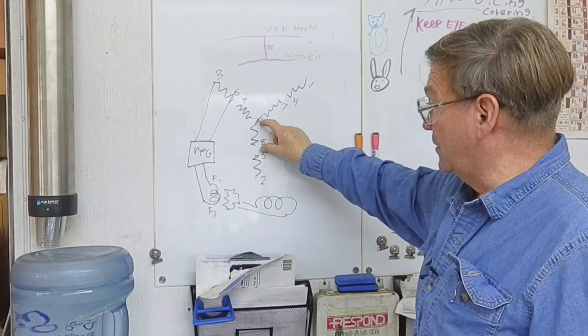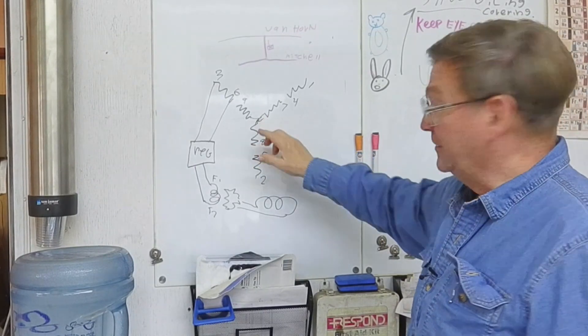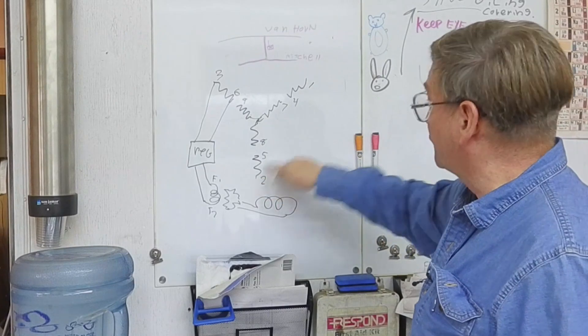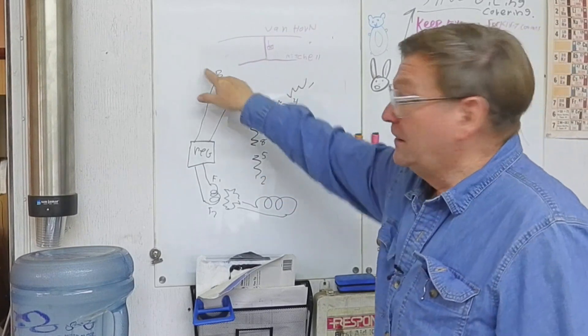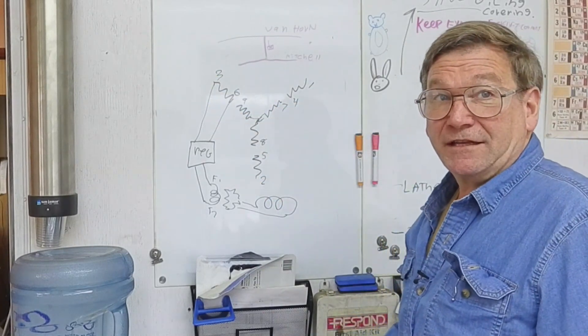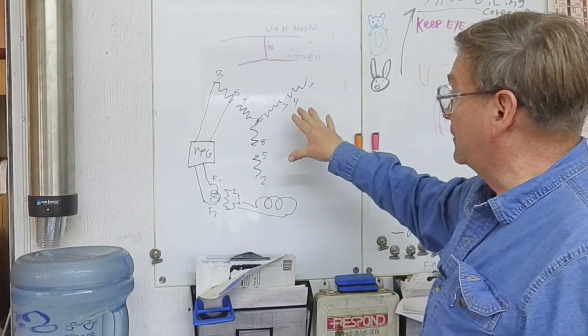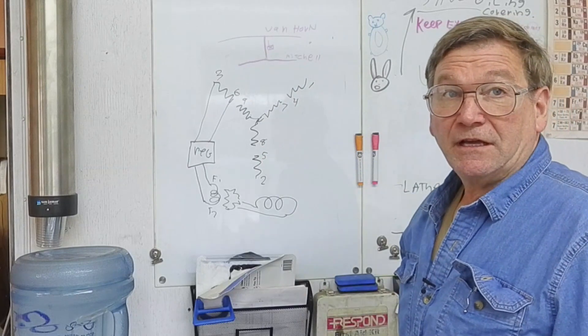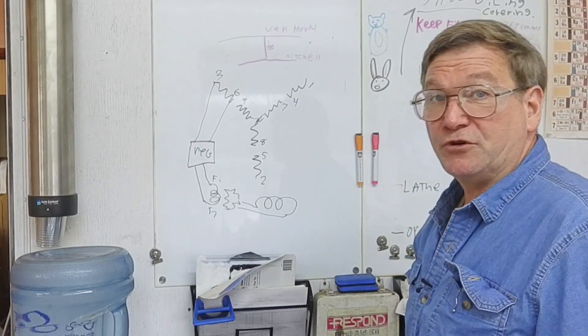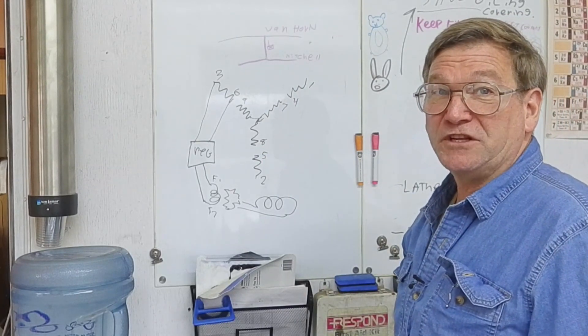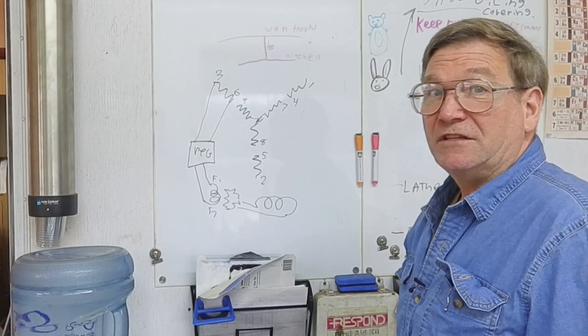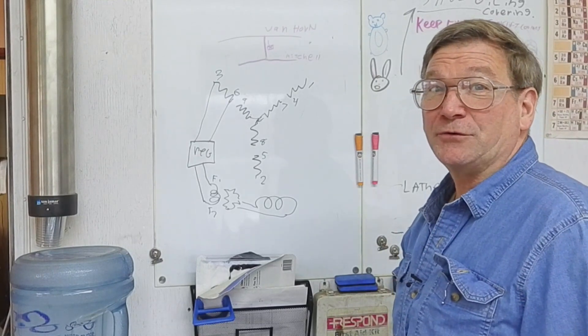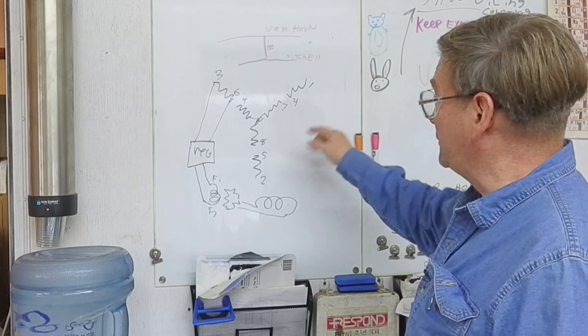Each of these coils are 120. Because of the angle is why you get 480 between here. That also depends on what your regulator is set to. But the big thing I wanted to draw out is the numbering system. While you'll find lots of books and charts that give you which number is which, they don't tell you how you can do it without having a book. And here's how you can do it.